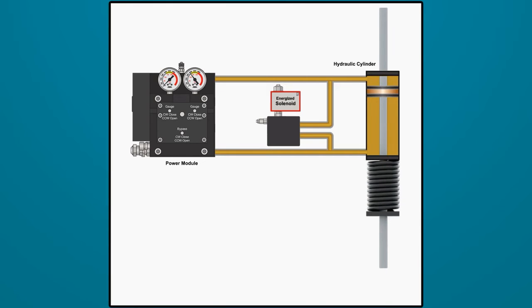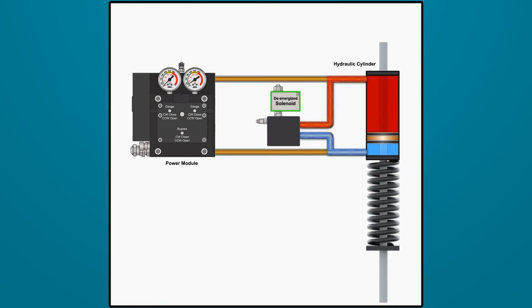In the event of a power loss or a trip condition, the solenoid is de-energized. This equalizes pressure on either side of the piston, allowing the spring to move the valve to its fail-safe position.